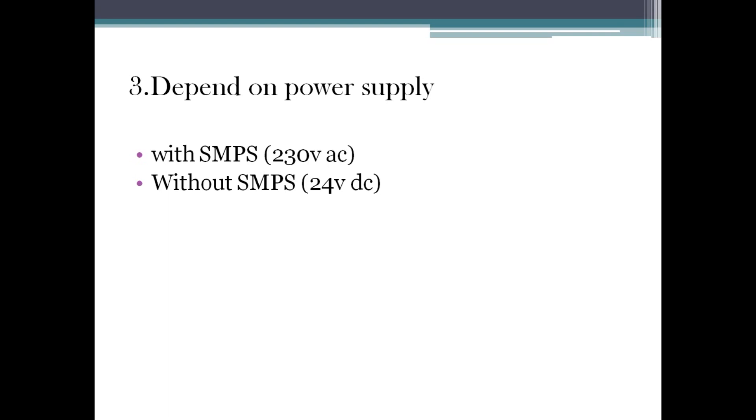Suppose if you are giving 230V directly to the PLC, that means the PLC is having SMPS component inside. PLC can work with 24 volt only, but in some PLCs you can give 230V also because it can convert 230V to 24V because it has SMPS inside. It's not visible from outside - if you open PLC you can see. That is with the SMPS PLC.